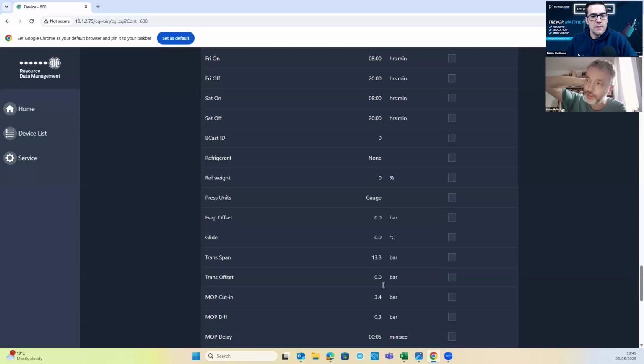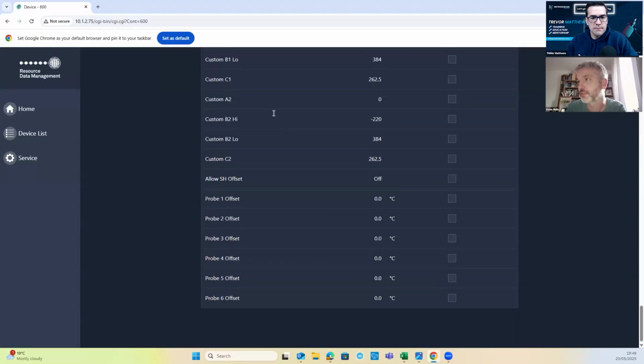Span from the bottom of the transducer to the top. So if it's a -1 to 65, your span is 66. Offset is, do I need to adjust the bottom end below 0? So if it's a -1 transducer, that will be -1. MOP, as we talked about. Custom settings for refrigerants and probe offsets.